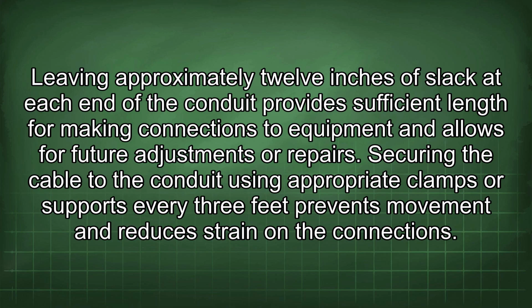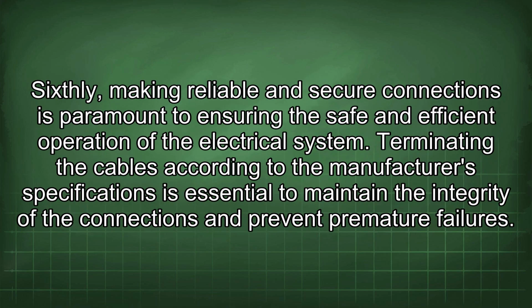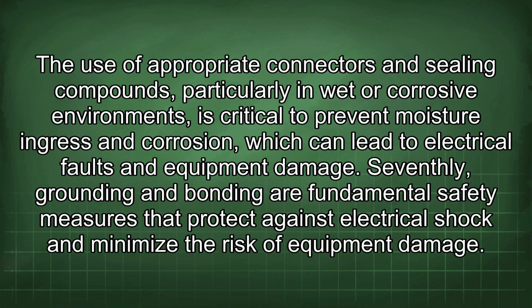the connections. Sixthly, making reliable and secure connections is paramount to ensuring the safe and efficient operation of the electrical system. Terminating the cables according to the manufacturer's specifications is essential to maintain the integrity of the connections and prevent premature failures. The use of appropriate connectors and sealing compounds, particularly in wet or corrosive environments, is critical to prevent moisture ingress and corrosion, which can lead to electrical faults and equipment damage.